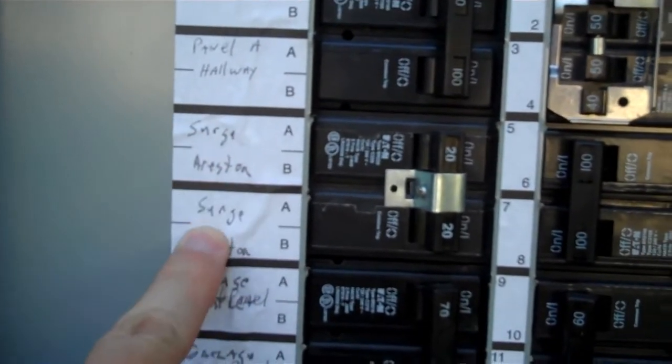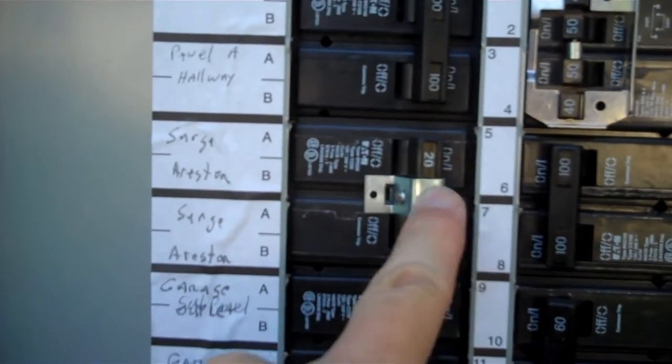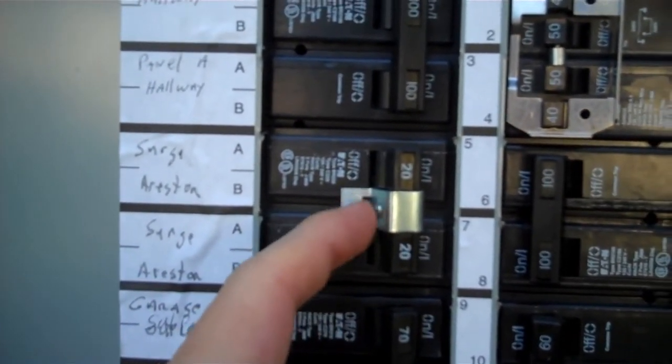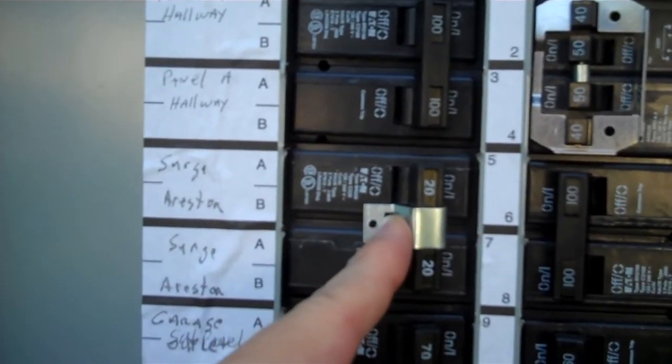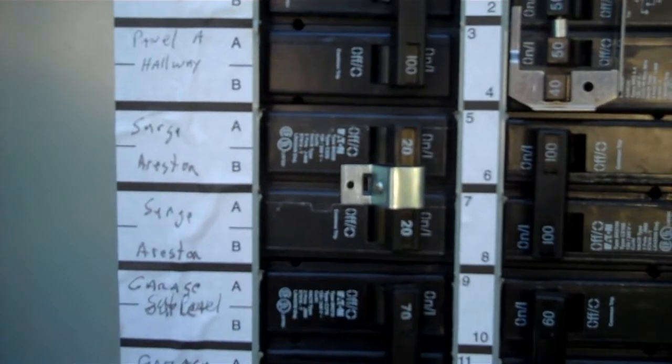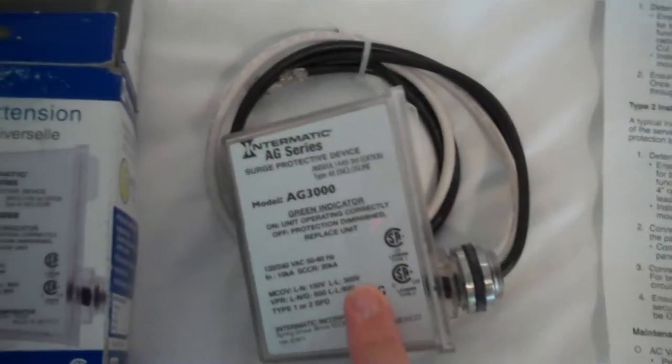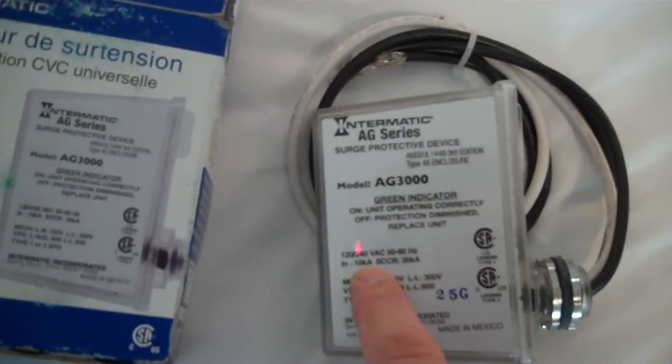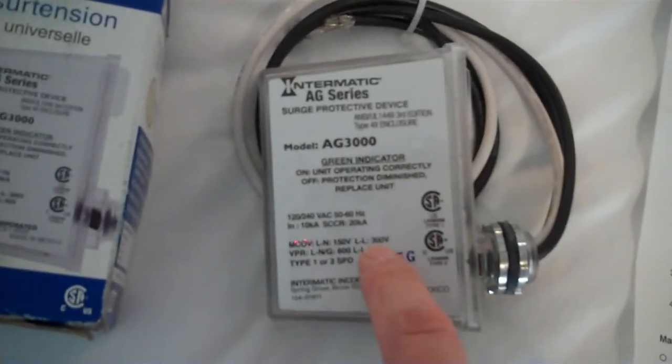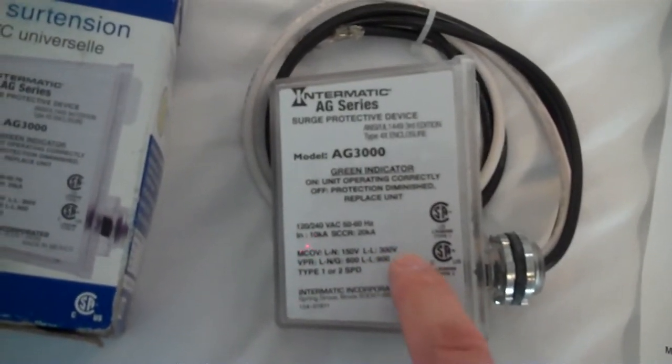So it's tied into my panel here on this surge arrestor, 20 amp, and you see they have a lockout tag here that basically will keep this guy turned on all the time. I used the model number to buy a direct replacement. You could have upgraded to something with a higher capacity, so this is 10 kiloamps. It is 300 volts line to line.